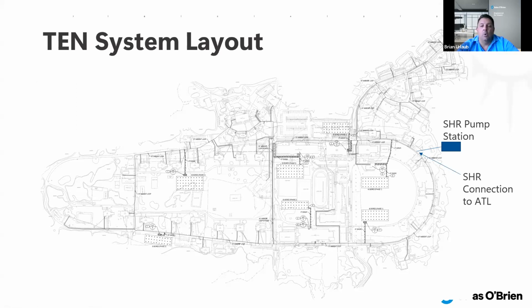Even though this is a single owner, we still want to maintain a buffer of maybe 5 to 10 degrees between energy sources, because we don't want heat pumps getting close to their operating limits. All this modeling uses average weather data, so you need a buffer in your design parameters to make sure that if you have an extreme weather event, you'll get through it without hitting the bottom or top end of your operating limits.